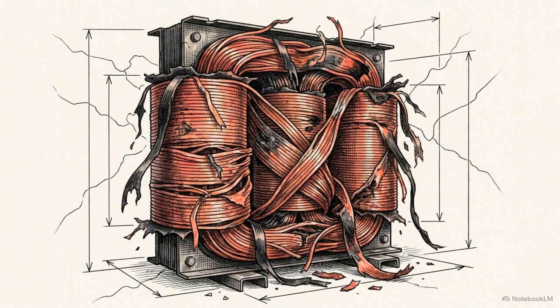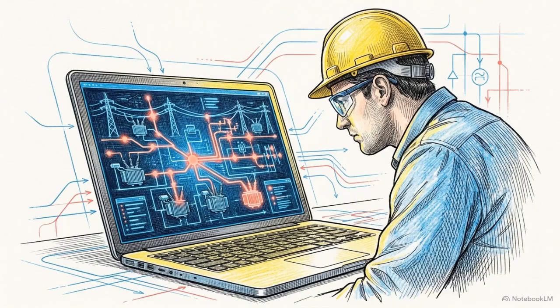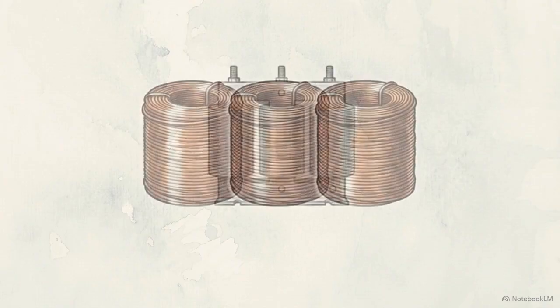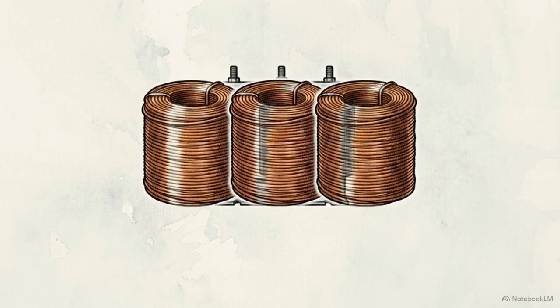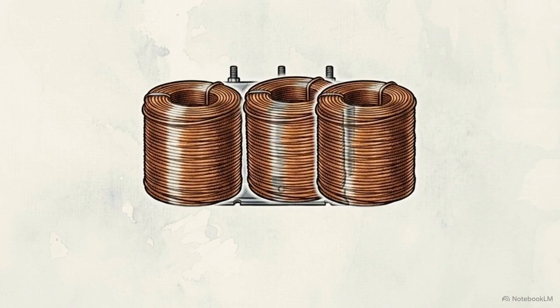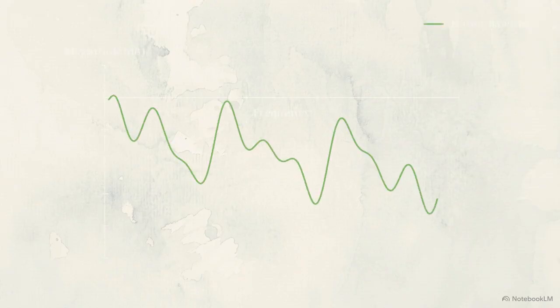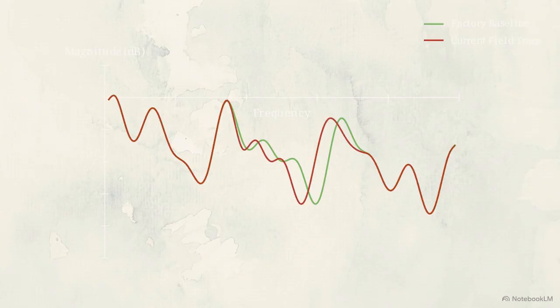Anomalous impedance data suggests either an error in the system fault studies or an internal displacement of the windings, which would compromise the unit's ability to survive a through fault. Analytically, we verify this mechanical stability by comparing field FRA traces directly against the factory baselines. Frequency shifts in the mid-band ranges act as clear indicators of radial deformation or winding displacement.